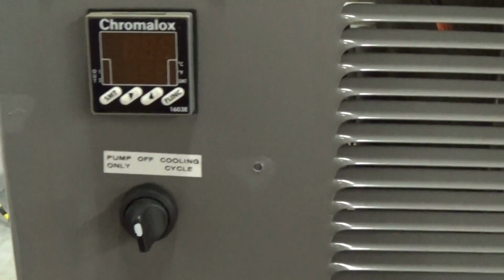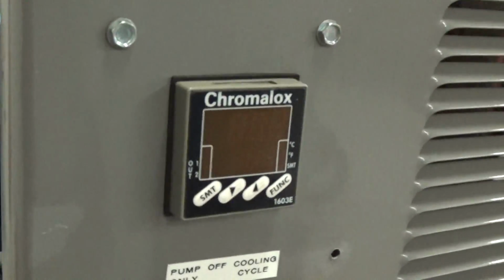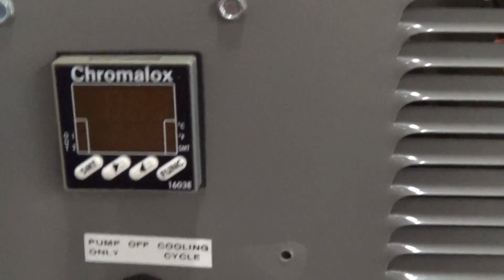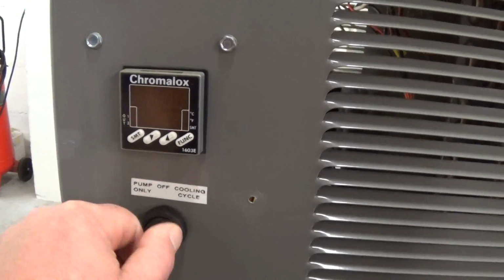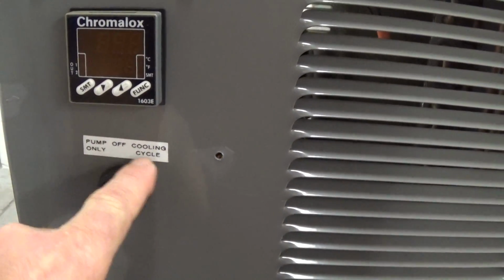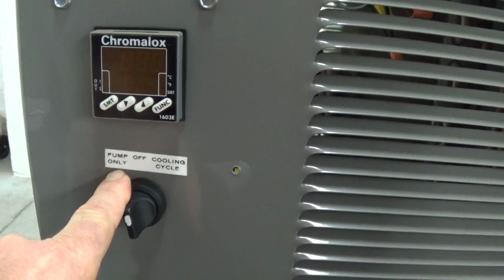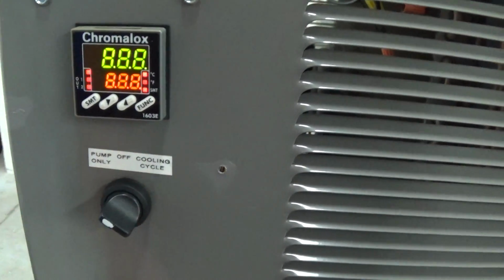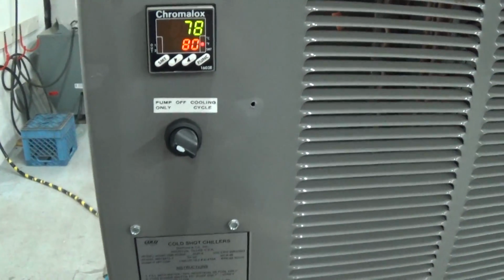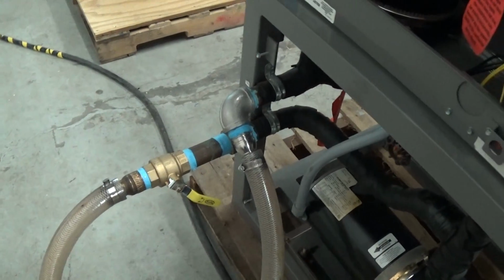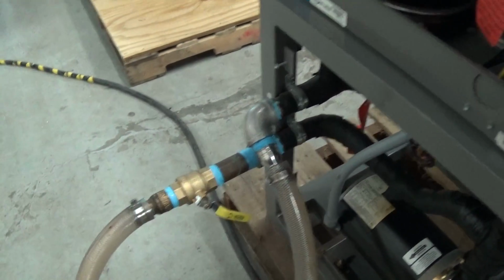We've been running it for a week or two now. Really didn't have to do much of anything to it. A few adjustments on the controller and on the thermal expansion valve, and confirming some things on the pressure switches. You have basically your off, your cooling cycle, and your pump only. We'll turn it on to the pump only right now. And we just got a little bit of a loop set up here, with a shut off to give our pump a little bit of back pressure.